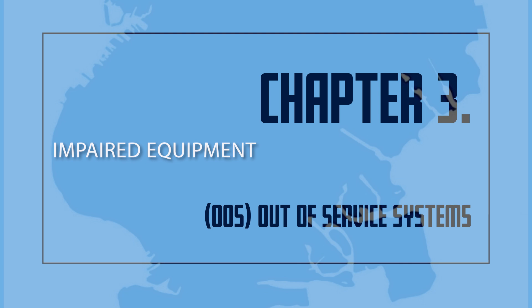Tags placed at control valves shall indicate the level of impairment or defect as follows: system fully out-of-service — red tag, white disk; system partially out-of-service — red tag, blue disk; system appears free of defects or deficiencies — green tag, no disk. Only FDNY, owner, MFSPC, or MLP as restricted may place a tag on a system. For systems that are fully or partially out-of-service that are not equipped with fire department connections, the appropriate tags shall be placed at the main control valve. FDNY is to be notified immediately.